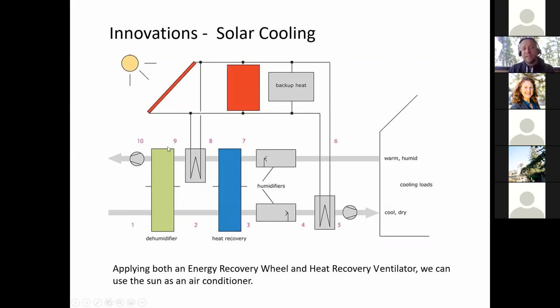But as I'm drying out the desiccant in this wheel, that means the incoming fresh air, so item 1, will actually get dehumidified in step 1, from 1 to 2. From 2 to 3, it's getting cooled down by that heat recovery exchanger. So now it is dry, cool air. I can add a little bit of humidity back to it to make it even cooler, as cool as possible. And then if I heat it up a little bit, it won't be cold, but it'll be cool, relatively dry air. So in this cycle, with no compressor, no heat pump, you could actually design a system to provide relatively cool, dry air driven by solar only.